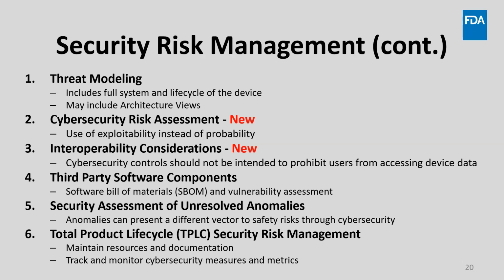For the cybersecurity risk assessment, we've added this section in order to more clearly identify the documentation deliverable. We recommend that you use exploitability instead of probability to assess cybersecurity risks, as these risks depend on a human actor or a cybersecurity threat that can't be modeled using traditional deterministic methods such as probabilities. Interoperability considerations were also added in order to underscore the considerations for cybersecurity controls when having an interoperable device. The cybersecurity control should not be intended to prohibit users from accessing device data, but should be used in order to ensure that interoperability can be done safely and securely.